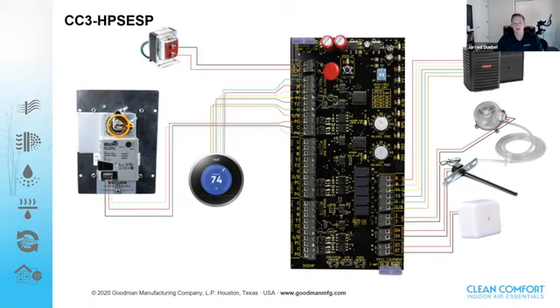No adjustment needed there. And then on the high limit, we give you the opportunity to adjust it if you'd like to. Using these dip switches, you can adjust it anywhere from 130 to 160 degree discharge air when you're in heating mode. If you want to make use of those features, you simply are going to install just a 10K ohm discharge temperature sensor. You're going to wire it right back to these DA terminals on the panel. The next thing you're going to see here, again, this is my heat pump version or dual fuel version. We have these 2 setting switches, or these 2 potentiometers. What these are for are high and low balance point settings. So if you install the outdoor temperature sensor, again, completely optional, it's going to wire right back to these OT terminals.